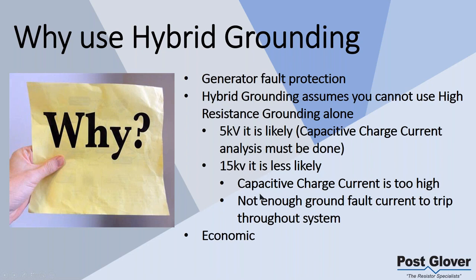And usually at the medium voltage of 15 kV, you're going to need higher ground fault current to be able to see your faults. Your relays are going to need more current to see your faults throughout the system. Although I will tell you that we definitely see high resistance ground systems being used at 15 kV for generator protection. That for sure happens all the time. So it can be done, but just keep in mind what the parameters are.